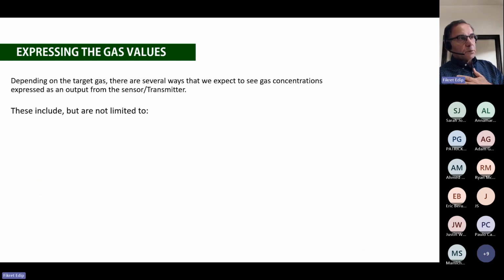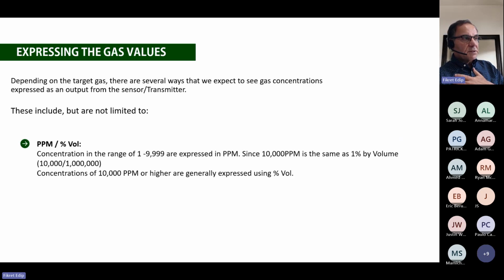How do you express the gas values? They are expressed in parts per million, or as I said, parts per billion, or percent volume. Now, a lot of people ask me this question: what is the difference between ppm and percent volume? Any value between 1 ppm and 9,999 ppm, we say it's 500 ppm, 600 ppm, or 9,000 ppm, etc. But the moment you hit the 10,000 ppm mark, it's becoming too much. So each 10,000 ppm is equal to 1% volume. In other words, 1% volume is 10,000 ppm.